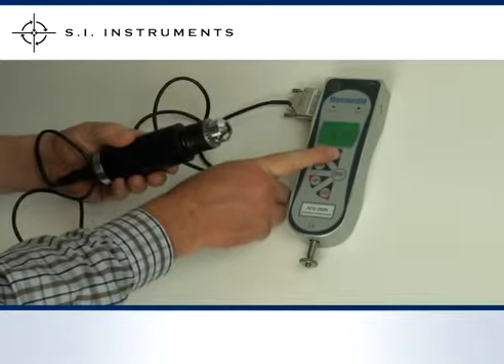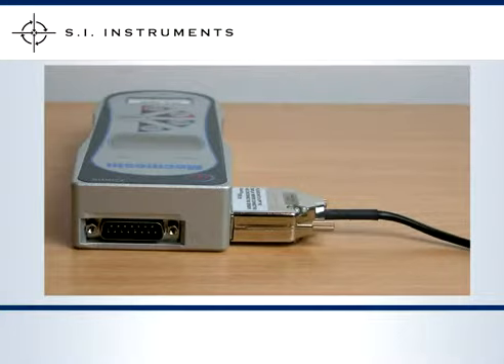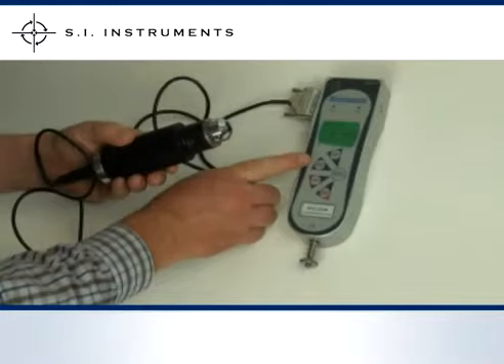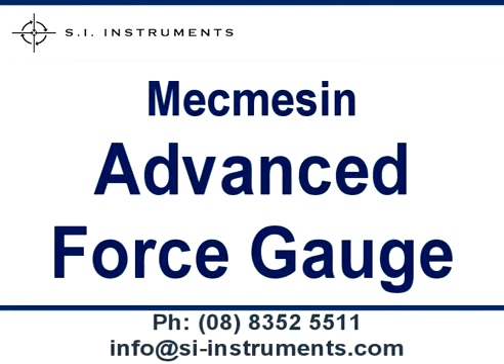As you can see, the communication port is still fully exposed. This means that all communication features with the unit are still possible even with the external transducer connected. Whilst the external transducer is connected, the internal load cell is not in use. Please refer to the PDF brochure of the Mecmesin Advanced Force Gauge for a complete overview of all possible force and torque sensors that can be connected.